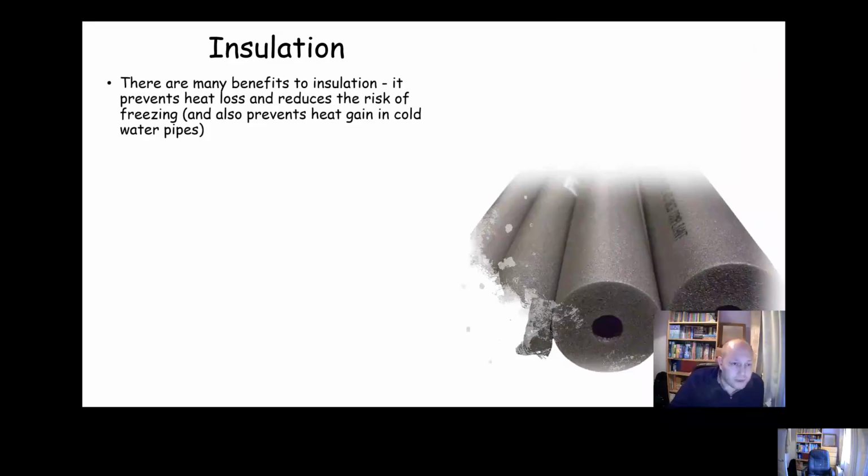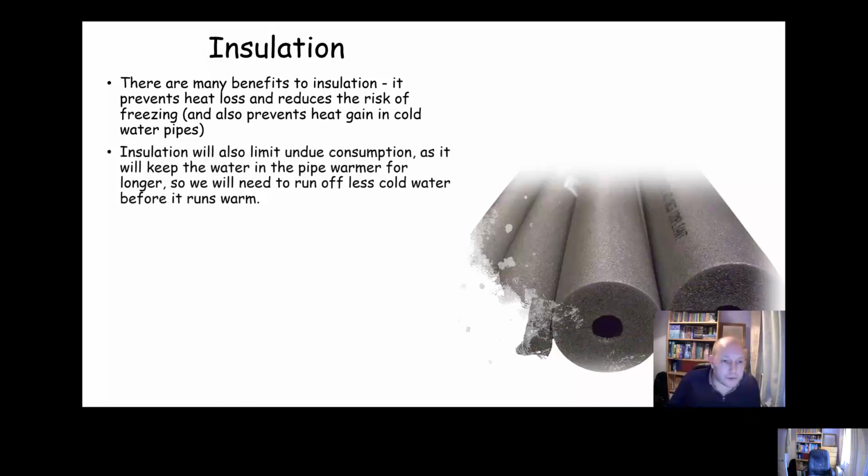So there's lots of different benefits to insulation. It helps prevent heat loss, and it also reduces the risk of freezing. And interestingly, it can also prevent heat gain in cold water pipes. If you have hot and cold water pipes running close together, the hot pipe can actually start to heat up the cold pipe, which can cause risk of Legionella.